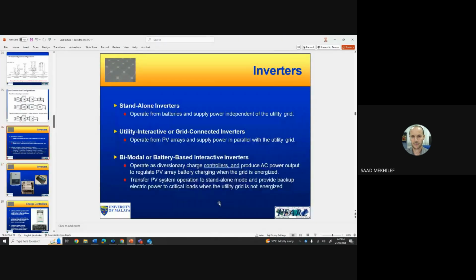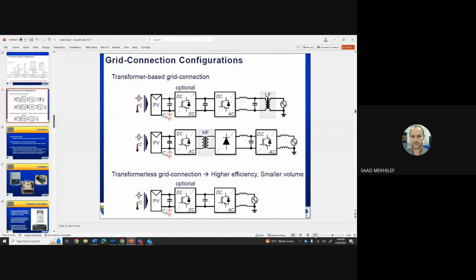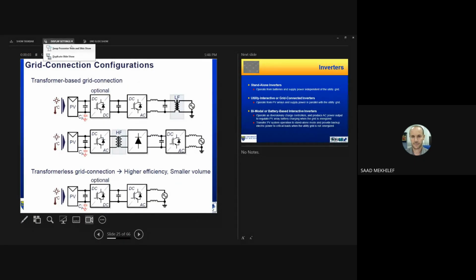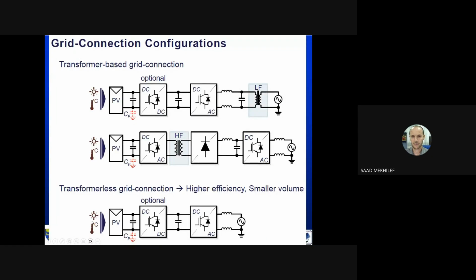Correct, very correct. In the transformer-based inverters there is total isolation, because the fault cannot transfer through the transformer. In transformerless, the PV is connected directly to the grid, so power can flow. That's why I say these other control techniques mean you need to be able to detect the fault on the grid and isolate your system. So the control becomes more complex compared to the transformer based.